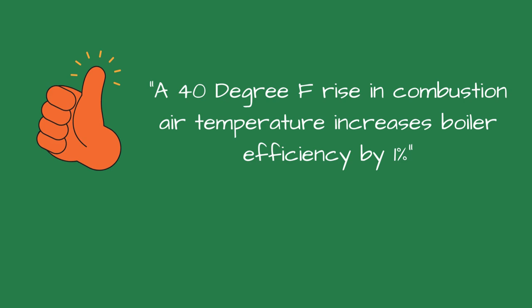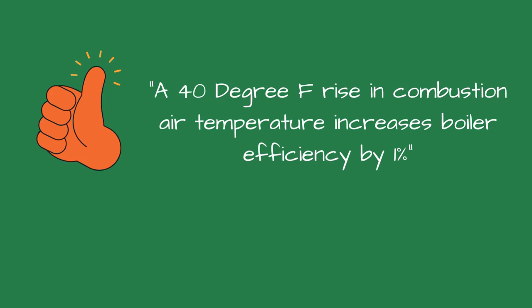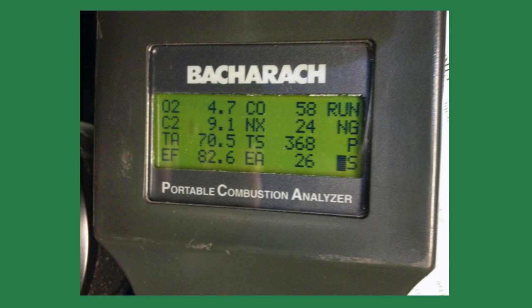An industry rule of thumb suggests a 40 degree rise in combustion air temperature results in a one percent increase in boiler efficiency. The problem occurs if you had the same teacher as I did — I was taught to always set the boiler air to fuel ratio on the coldest days. On a warm day, the hydronic loop heats quickly or the steam pressure rises and shuts off the boiler, and it takes forever for the loop temperature or pressure to drop and the boiler to restart.